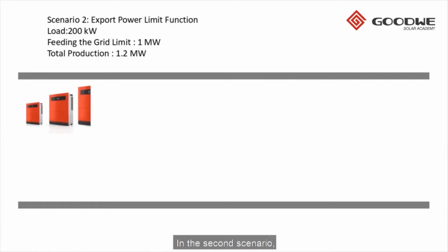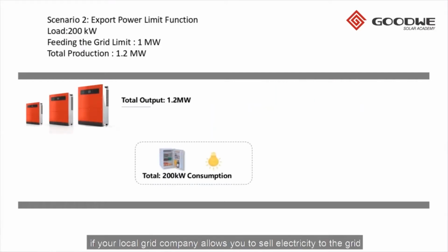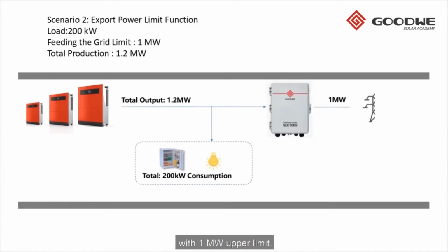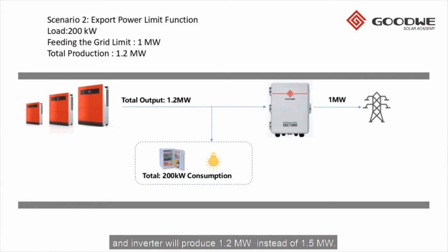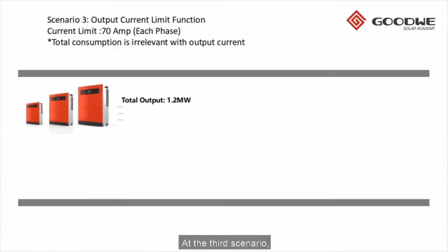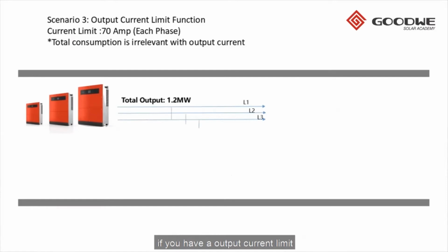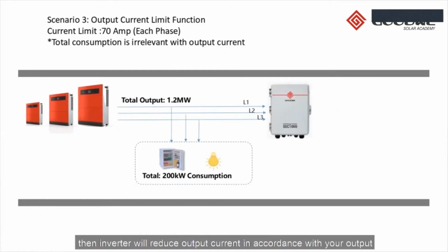the grid. In second scenario, if your local grid company allows you to sell electricity to the grid with 1 megawatt upper limit, then we have to use export power limit function, and the inverter will produce 1.2 megawatts instead of 1.5 megawatts. 200 kilowatts for providing energy to your own consumption, and 1 megawatt directly goes to the grid. In third scenario, if you have an output current limit such as 70 amps per each phase, then the inverter will reduce the output current in accordance with your output current limit.